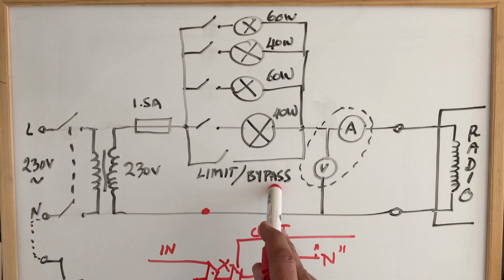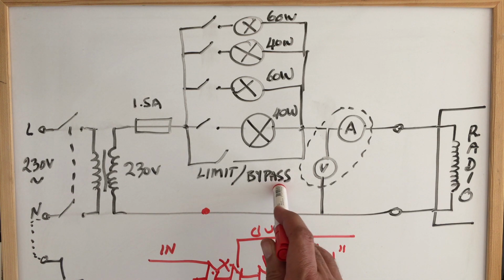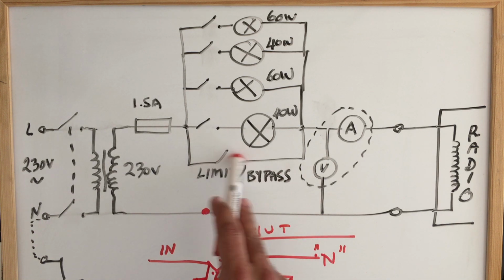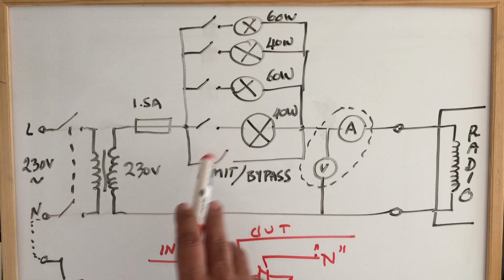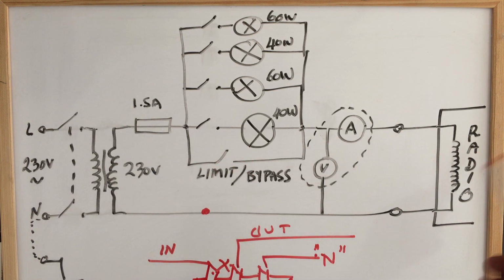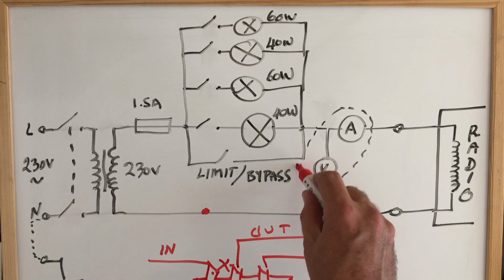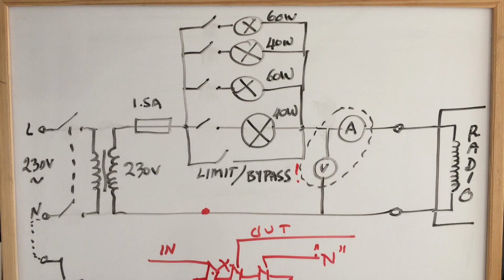The limit bypass switch is always a risk, because you may forget to open it—in other words switch it off—and put something in there that's got a short, and then your whole limit function is bypassed, and you'll probably end up with fireworks anyway. So you have to be very, very careful with this. On the front panel, I've actually marked an exclamation mark over there. And this is basically it.